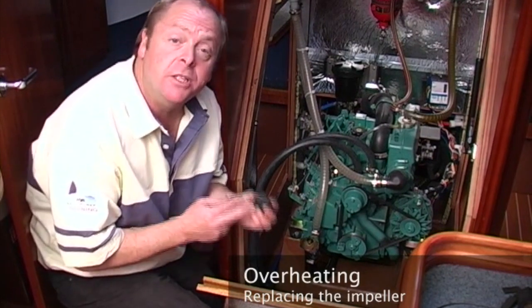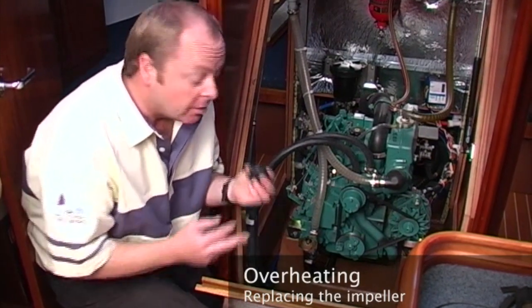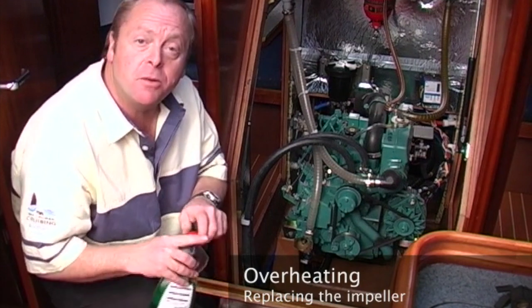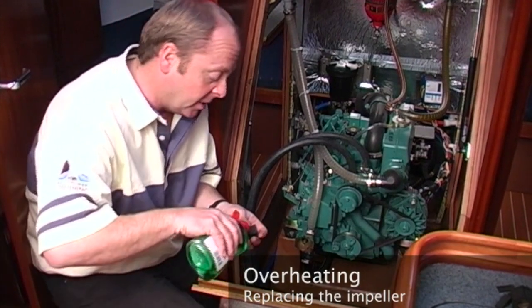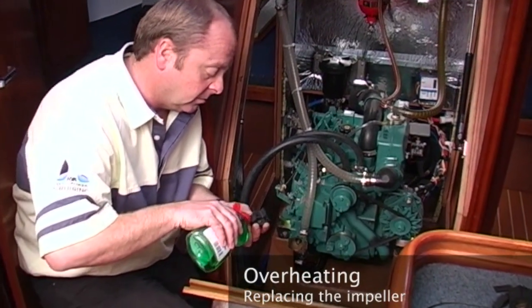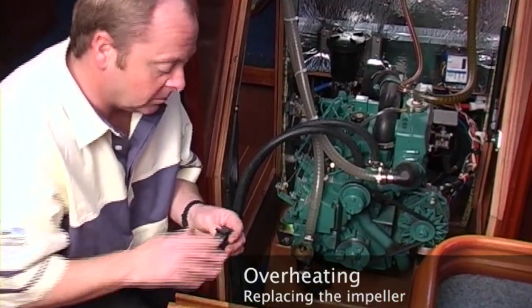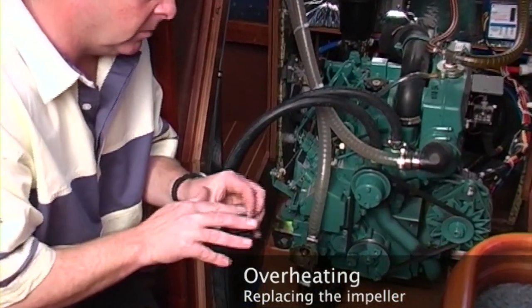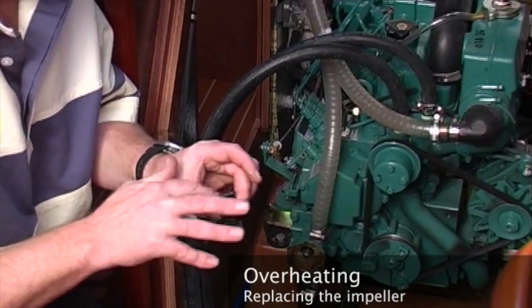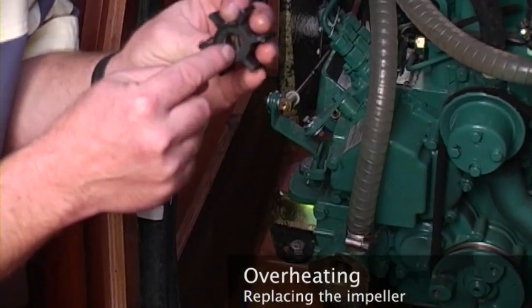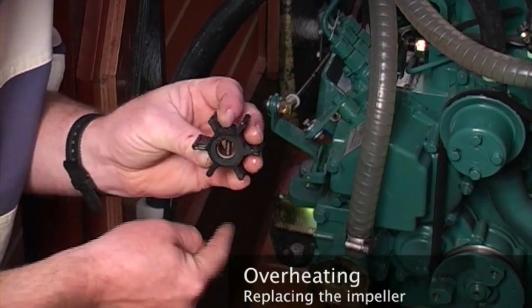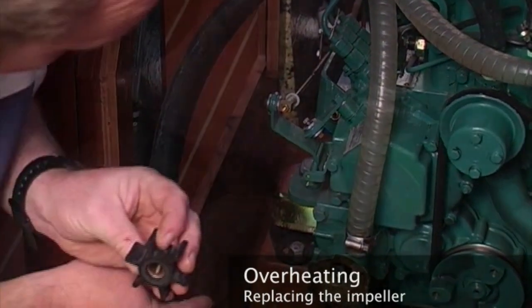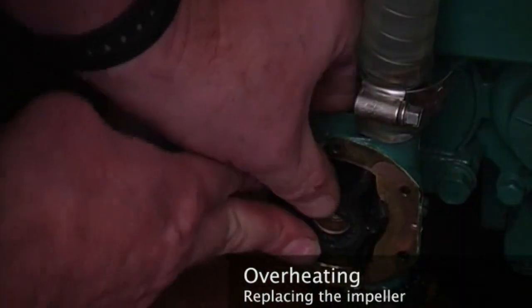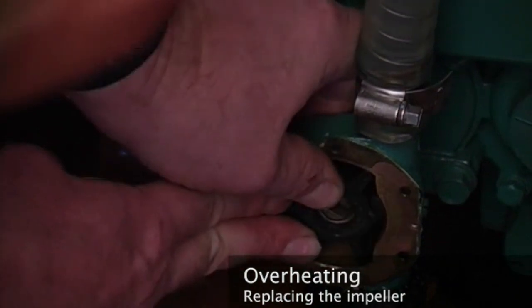We're now going to put in the new impeller. First, cover it with a bit of washing up liquid to give it some lubrication. This impeller has a grub screw going through the centre, which goes into a slot on the shaft. Line them up, place the impeller in like this, and gradually push it home.